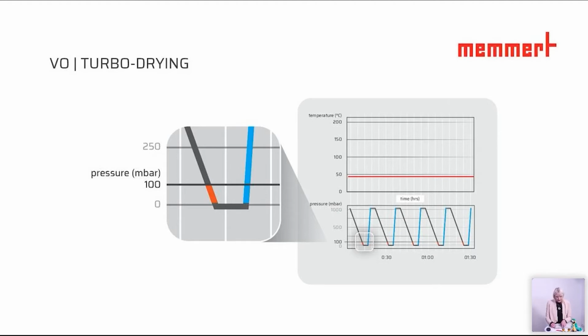And then it means here we take out the humidity in a fast way, and when we go up again in pressure and air enters, the vaporized water is sucked up like by a sponge. And that is what we see on this blue line. So that is how this works and how these digitally controlled programmed ramps are efficiently used in our Memmert vacuum oven. That is really a big advantage for very fast drying processes.